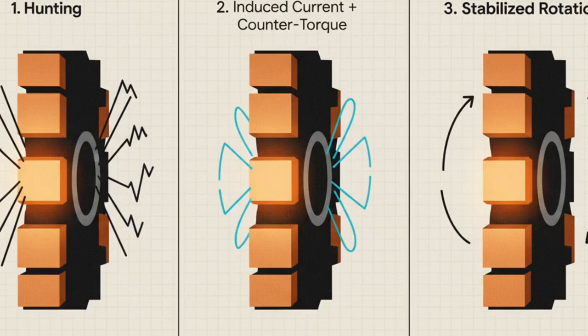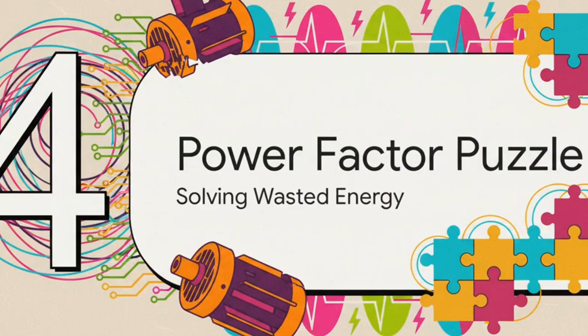So what about that wobbling problem, hunting? Well, the solution is just beautifully elegant. Engineers embed these special copper bars called damper windings right into the rotor. Now, when the motor's running stable, they do absolutely nothing. But the second the rotor starts to oscillate, that movement creates a current in the bars. That current creates its own magnetic field that pushes back against the oscillation, effectively damping it and making the motor stable again. It's brilliant.